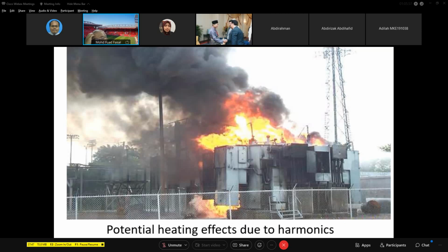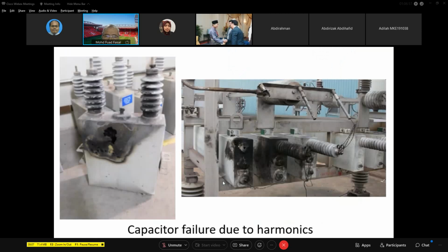Okay, this is a newspaper article from overseas, in Brazil. From the newspaper itself, after the firemen extinguished the fire, there was a study done. Based on the report that I've read, they said that the transformer overheated due to harmonics. That's what they reported in the newspaper. Okay, this is somewhere near Malaysia. Power capacitors exploded due to overvoltage and harmonics. As you can see, there's a hole in the capacitor can on the left hand side. On the right hand side, you can see that the bushing of the capacitor can is broken, burnt, missing. All these are due to harmonics.